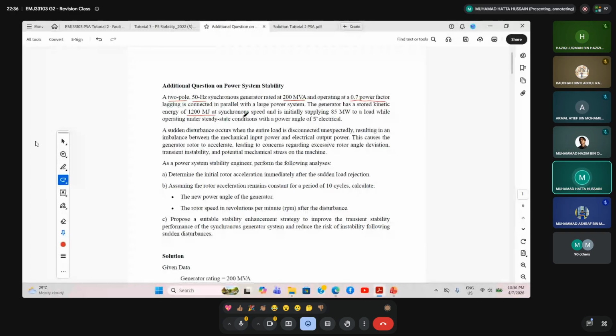And then we have it initially supplying 85 megawatt to a load while operating under the power angle of 5 degree. A sudden disturbance occurs when the entire load is disconnected unexpectedly, resulting in an imbalance between the mechanical input power and electrical output power. This causes the generator rotor to accelerate, leading to concerns regarding excessive rotor angle deviation and transient instability.